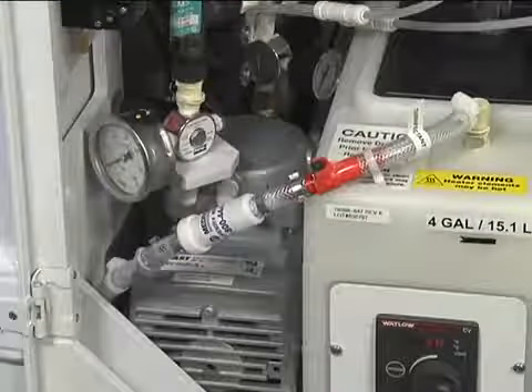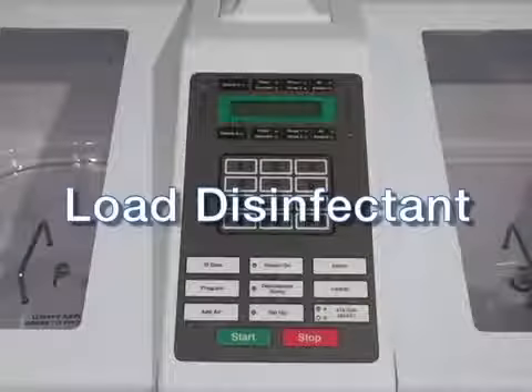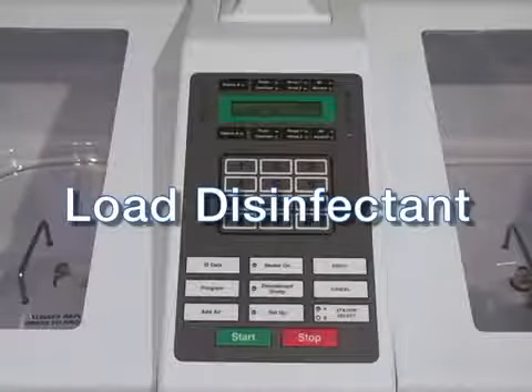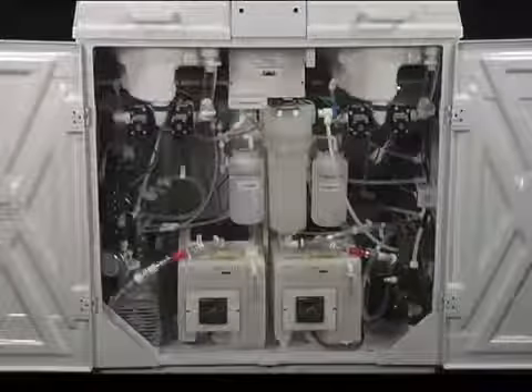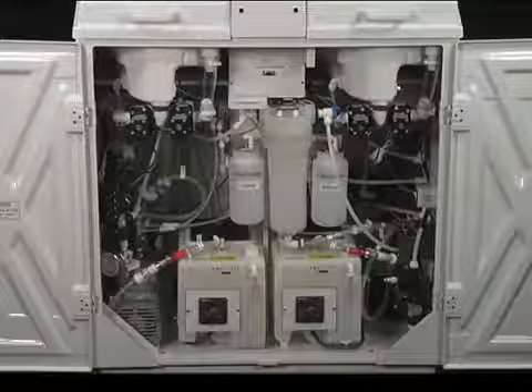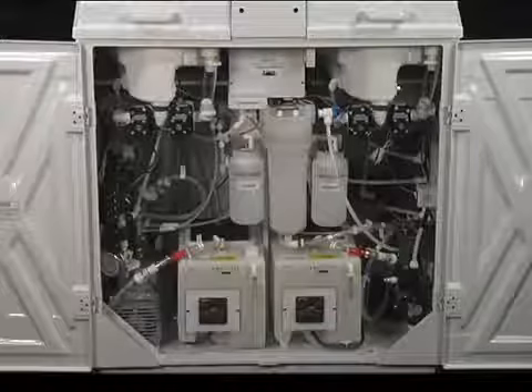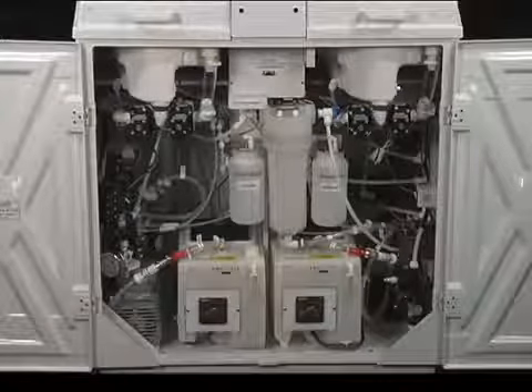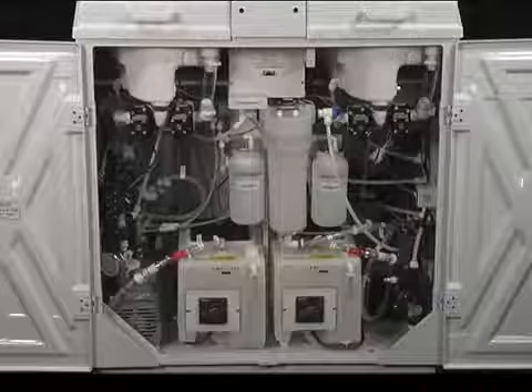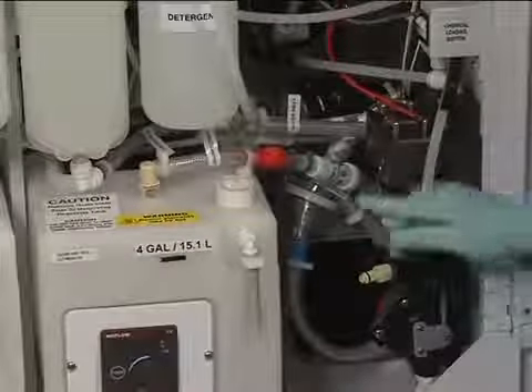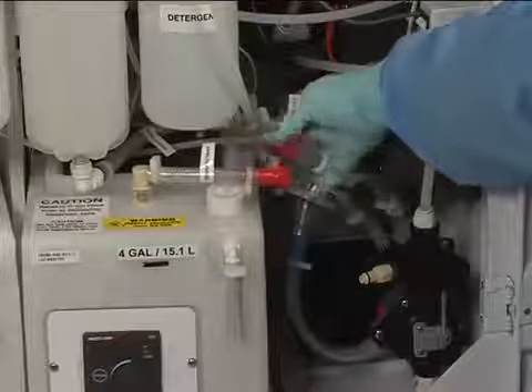You are now ready to load the disinfectant, automatically using the onboard transfer pump or manually with the load disinfectant function. The automatic transfer pump minimizes operator exposure to vapors by loading the disinfectant directly from the disinfectant container into the reservoir. To perform this, locate the reservoir to disinfectant filter connection and disconnect them at the red connection. Fully remove and replace the old disinfectant filter.